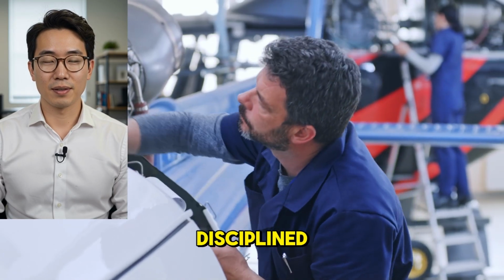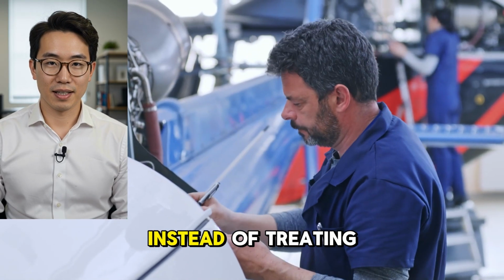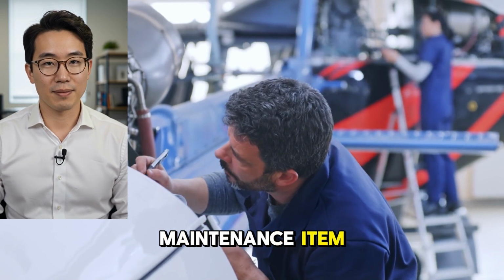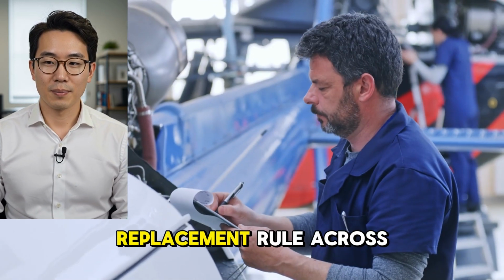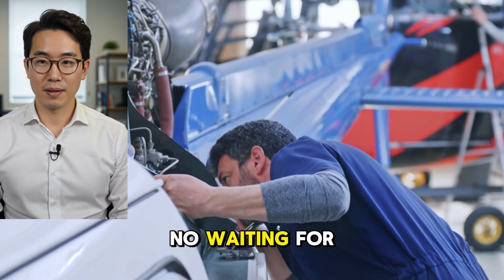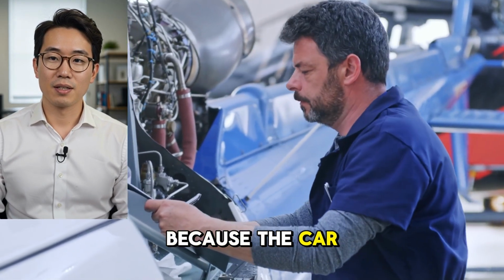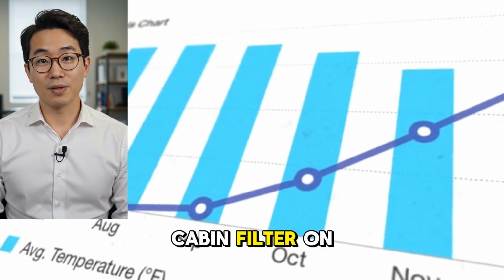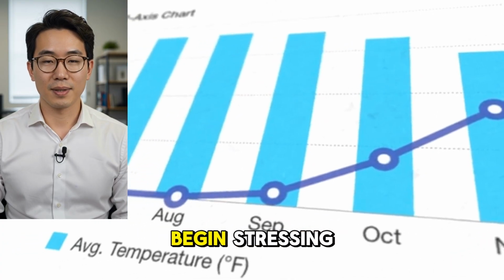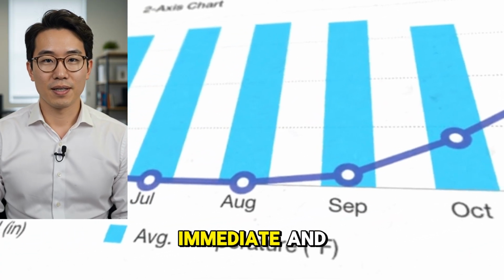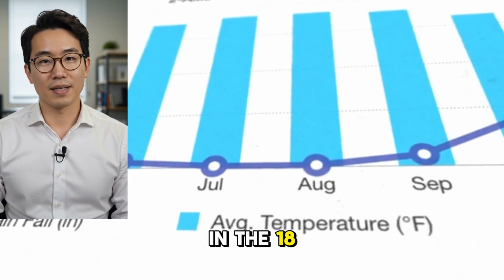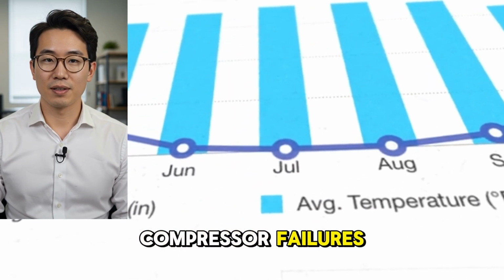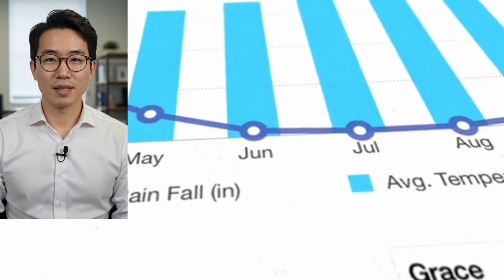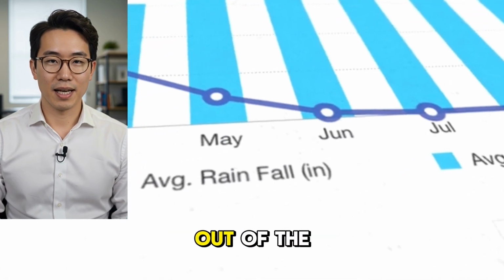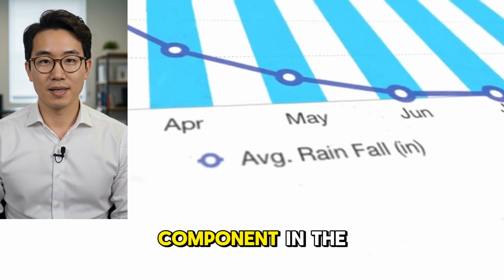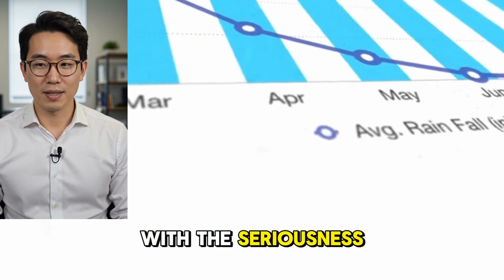Fujiwara's response was simple, disciplined, and devastatingly effective. Instead of treating cabin filter replacement as an optional maintenance item, he implemented a mandatory 12,000-kilometer replacement rule across the fleet. No guesswork, no waiting for complaints, no stretching service intervals because the car still seemed fine. Every vehicle got a fresh cabin filter on schedule before airflow could collapse badly enough to begin stressing the rest of the system. The result was immediate and impossible to ignore. In the 18 months that followed, the fleet recorded 0 compressor failures. Not fewer. 0. The expensive repeat problem that had been bleeding money out of the operation disappeared when the cheapest neglected component in the system was finally treated with the seriousness it deserved.